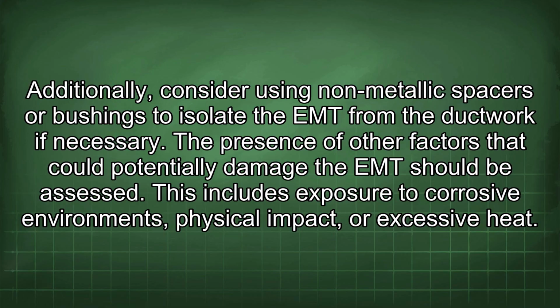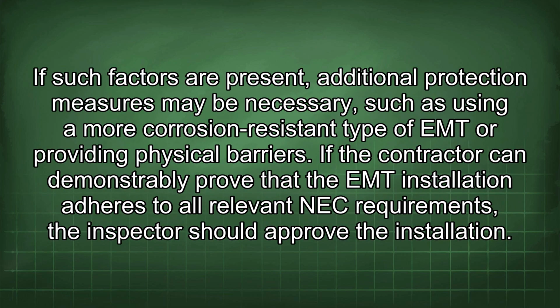The presence of other factors that could potentially damage the EMT should be assessed. This includes exposure to corrosive environments, physical impact, or excessive heat. If such factors are present, additional protection measures may be necessary, such as using a more corrosion-resistant type of EMT or providing physical barriers. If the contractor can demonstrably prove that the EMT installation adheres to all relevant NEC requirements, the inspector should approve the installation.